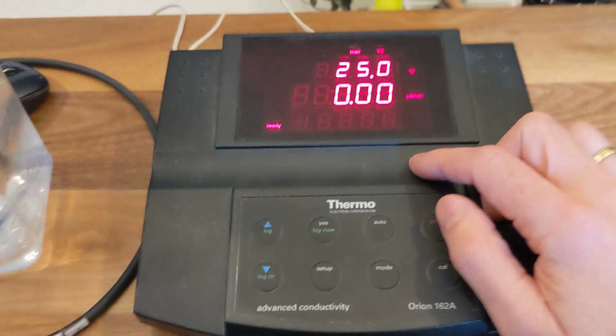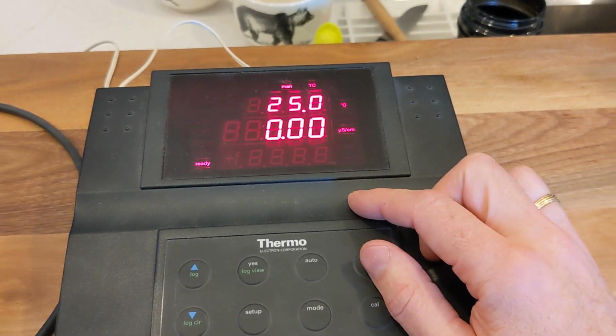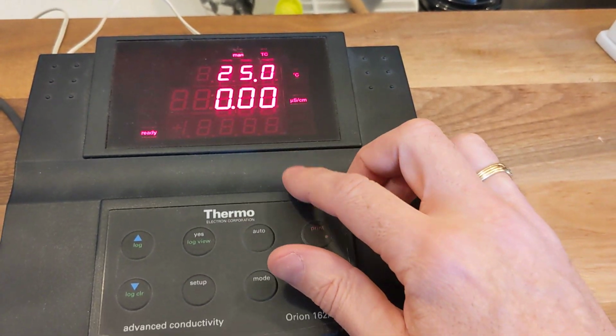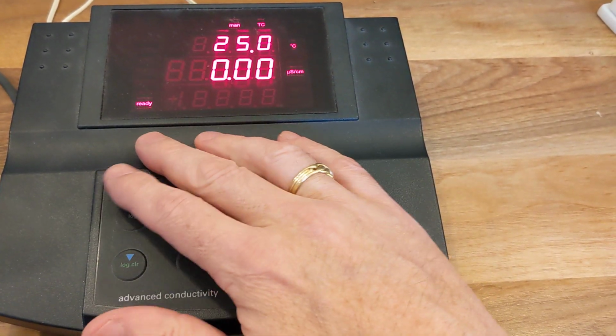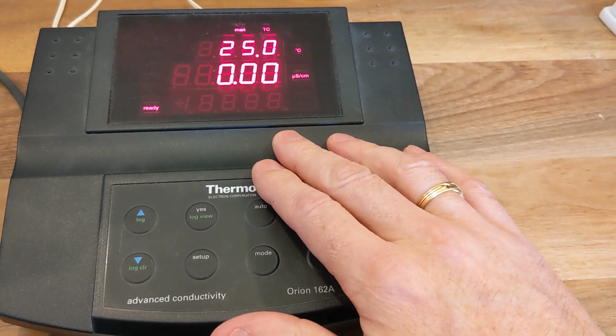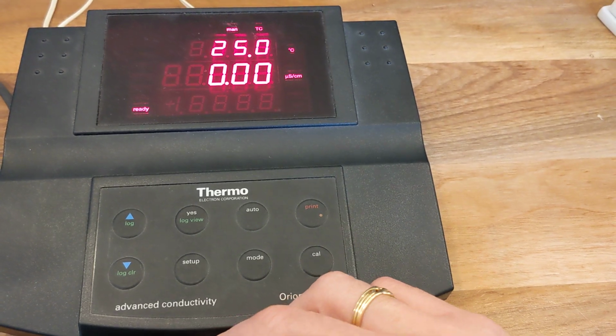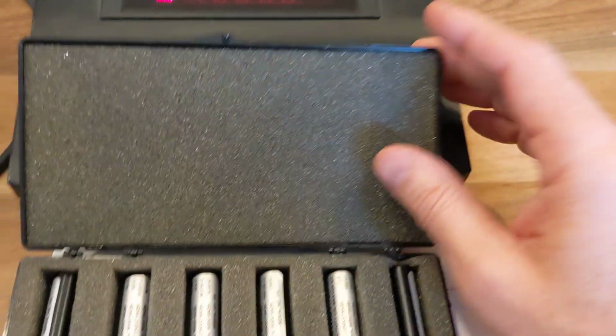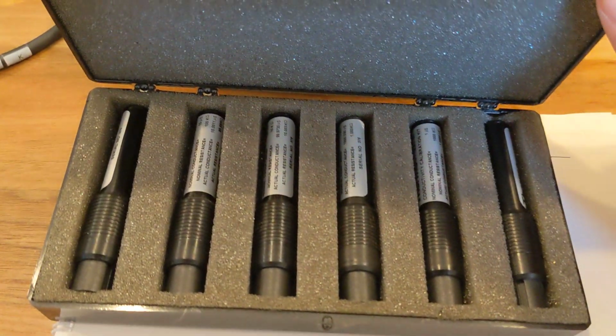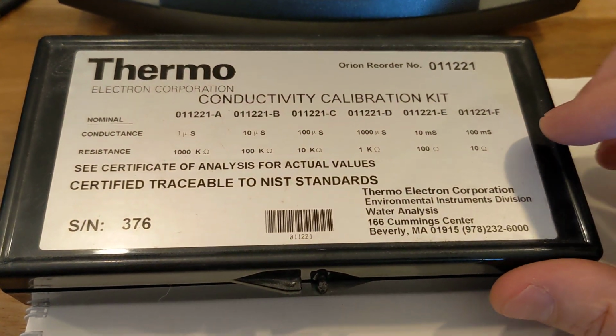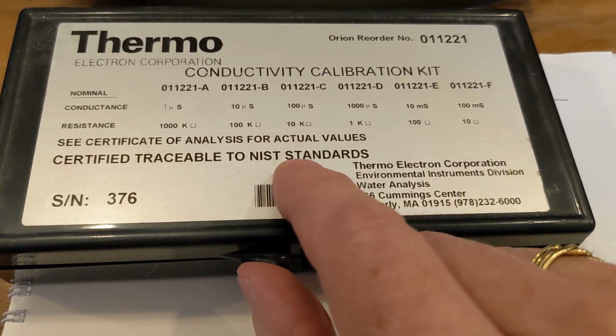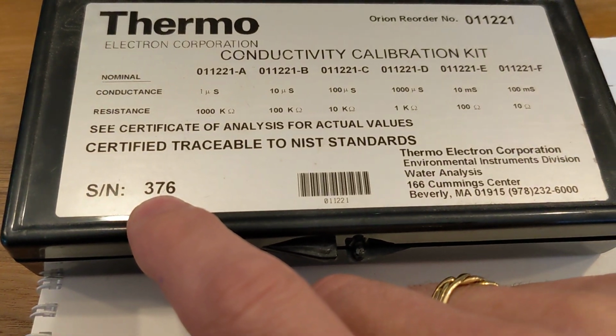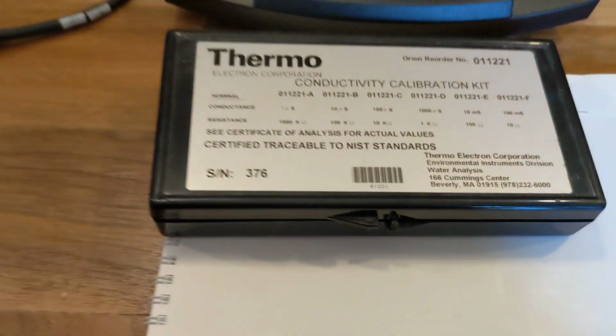Now, conductivity is an inverse of resistance, so it would stand to reason if you put a resistance across the input terminals of the conductivity meter, it's going to be able to tell you what the conductivity is of that resistor. And these are not just any old conductivity standards, but they are NIST traceable standards. And look at that, serial number 376. They've made 376 of those.